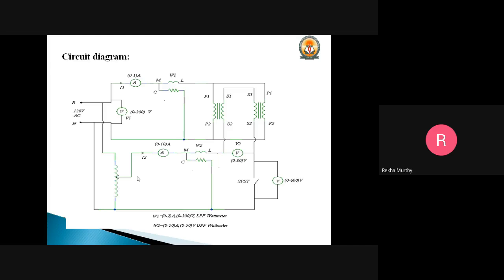Now let's go through the procedure for conducting this experiment. With the SPST switch kept open, make sure the autotransformer is at minimum position and then switch on the supply. The polarities of the secondary voltages of the transformer will be checked by using the voltmeter connected across the SPST switch — that is the 0 to 600 volt voltmeter — which is used just to check the polarities of the secondary voltages.